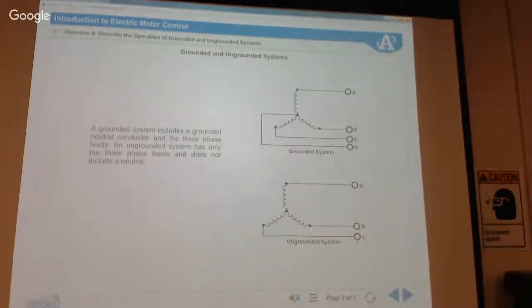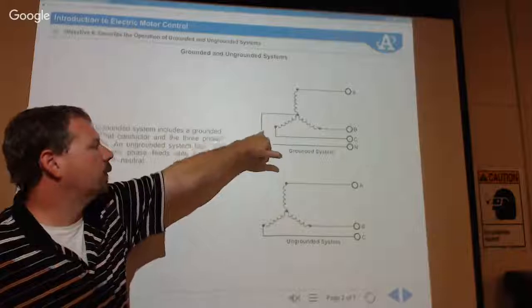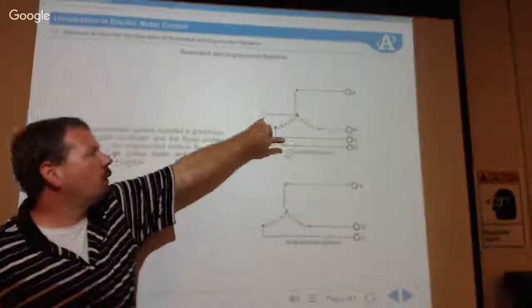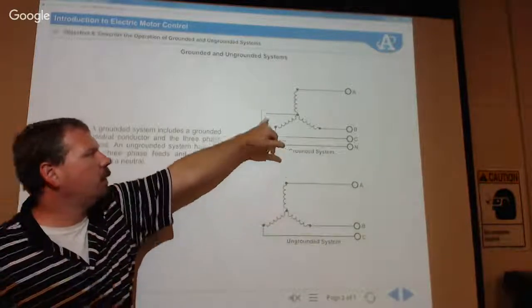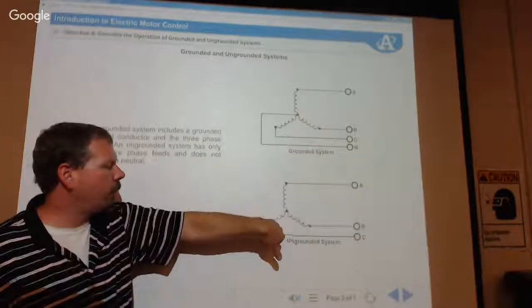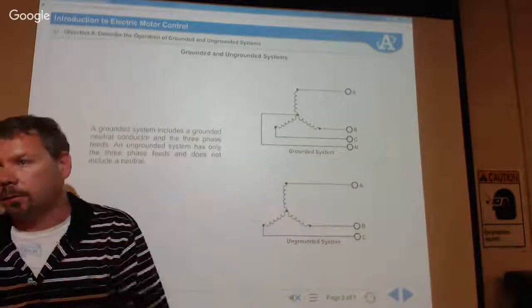So a grounded system includes a grounded neutral conductor and the three-phase feeds. An ungrounded system has only the three-phase feeds and does not include a neutral. What they mean by that is the center tap is not here. They're not tapping off here to give me a neutral for this configuration. See that? If I'm not going to run 120 volts off this transformer, I don't need that. All I'm using is three-phase power. I wouldn't need a neutral.